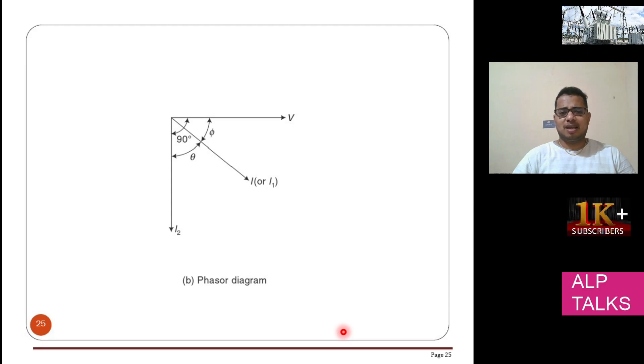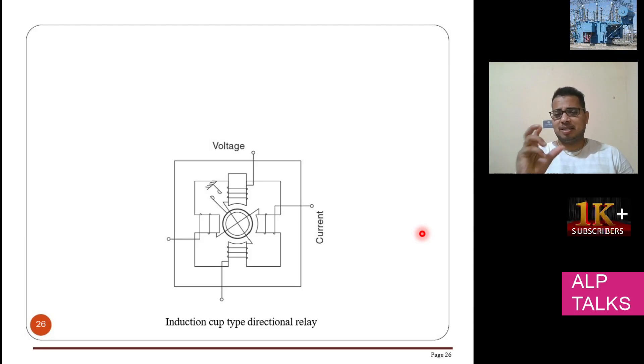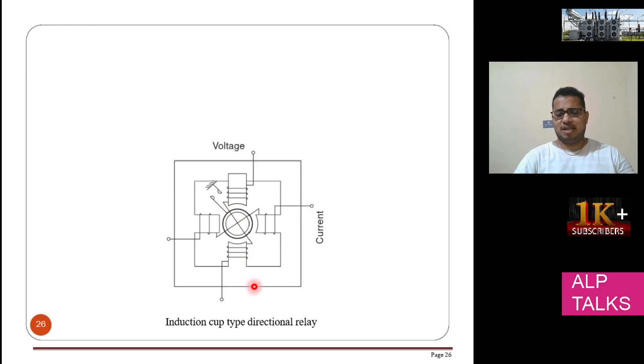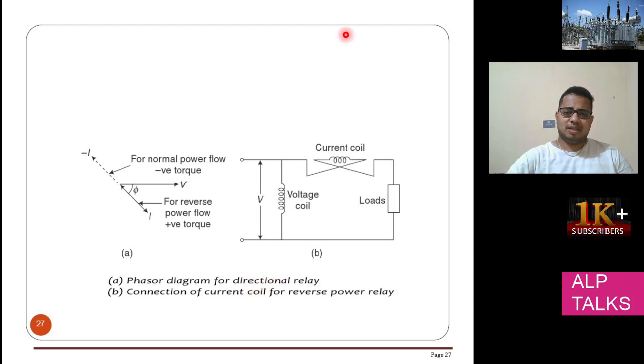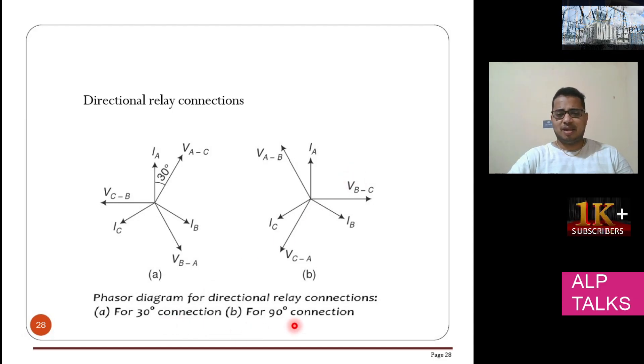This is the phasor diagram for the directional relay, where V and I are shown, and the current is lagging by 90 degrees. I1 is the secondary current and I2 is the compensating circuit current. Another version is the induction cup type directional relay, which has two different phases. One is current and another is voltage. You also have reverse and negative torque versus positive torque. The circuit diagram shows a voltage coil and current coil. There are two phasor diagram connections — type A for 30-degree connection and type B for 90-degree connection.